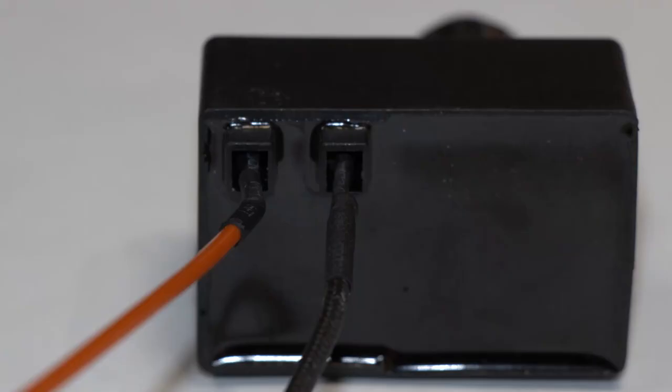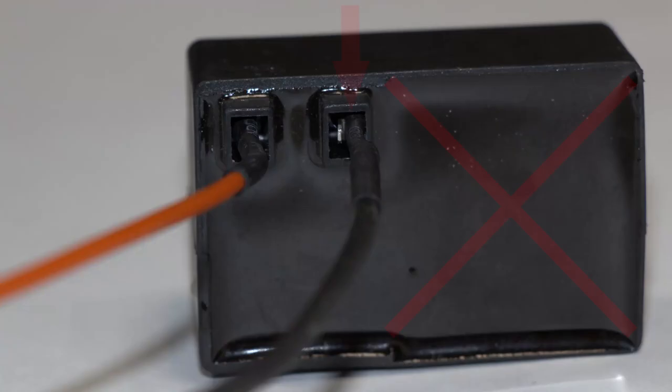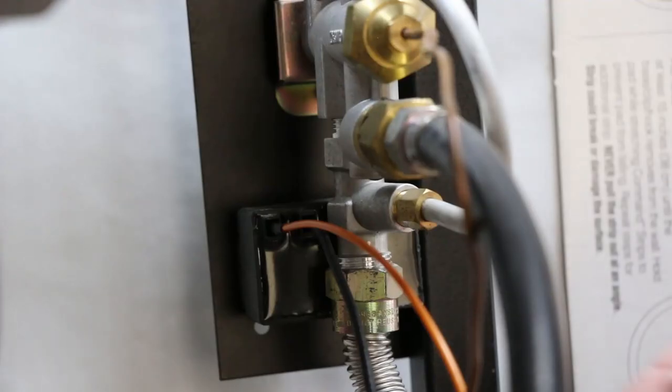Make sure the female ends of the wires are tightly fitted to the male ends of the sparker box. Small gaps on each side of the sparker box connections, as shown here, make it possible to wedge the wire connector in place, making it feel like it's actually connected when it's not. Retry the sparker.